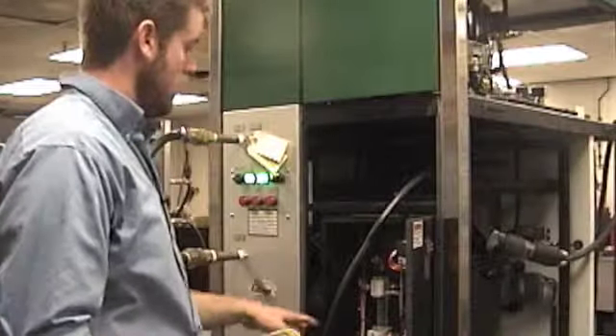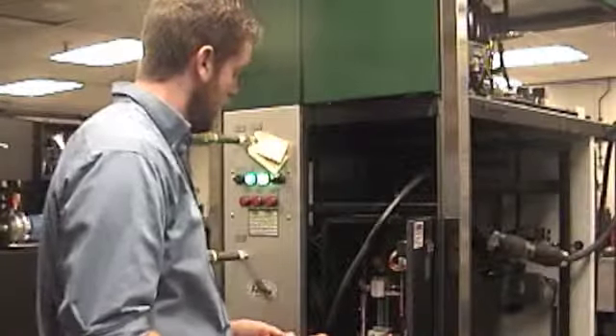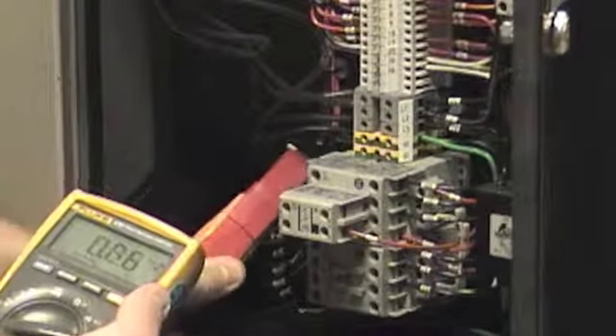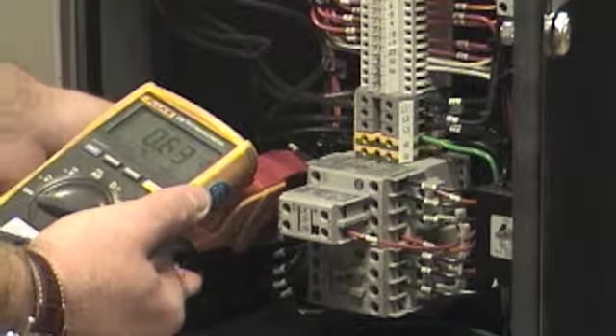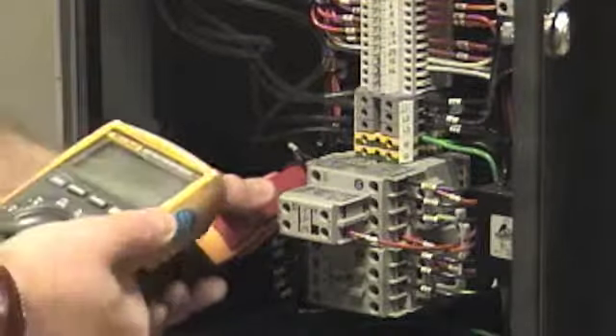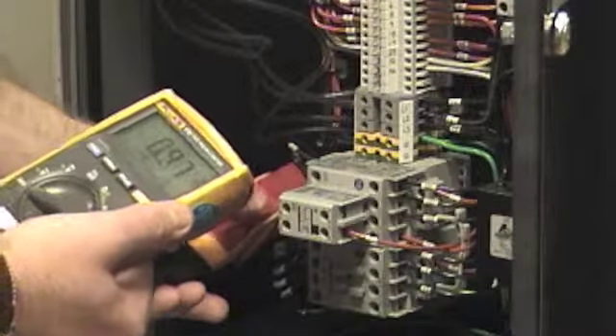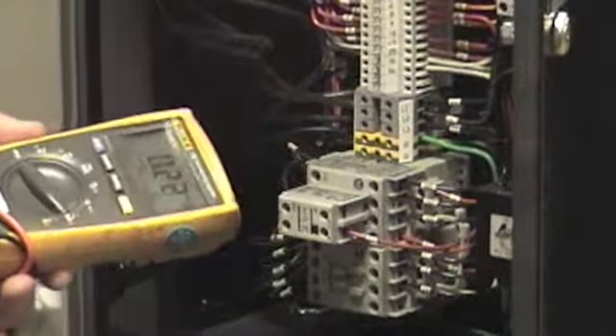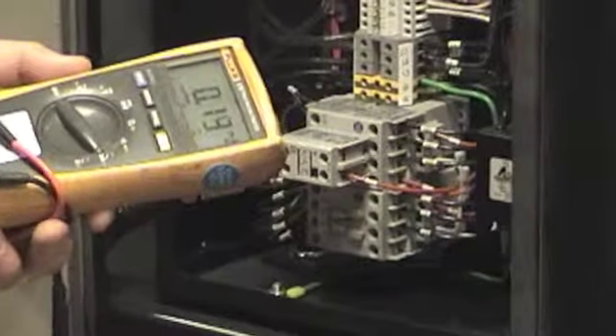So now, inside the electrical box, we're going to check our amps on each of the components. You'll want to check the legs and compare it to the tag on the inside of the unit. This particular one has a range of 1.3, and we're below that range on that leg. So we'll compare it to the second leg. We're well below it on that leg. And on the highest one, we're about 1. We're still well below the acceptable range. If we were too high for some reason, we can adjust the bypass valve that we just showed and open it a little bit, and that'll relieve some of the pressure on the pump and drop the amperage.